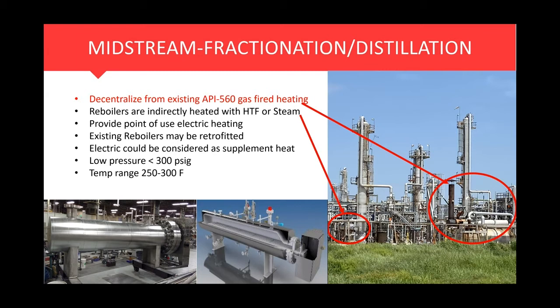Instead of increasing the size of your existing hot oil heaters with a retrofit or an additional hot oil heater, which will increase your emissions and require permitting, electric should be considered to supplement that heat with a zero emission alternative. Generally speaking, we have low pressures of less than 300 psig, temperature ranges from 250 to 300. The other alternative here is to use an electric steam generator versus a gas-fired steam generator. Or if you want to electrify the situation as well, just remove the gas-fired unit and go with an electric steam solution.